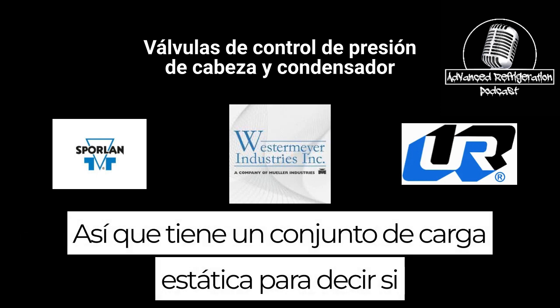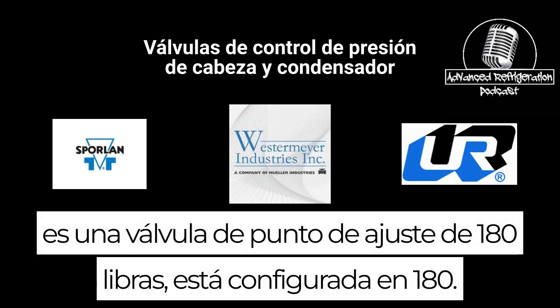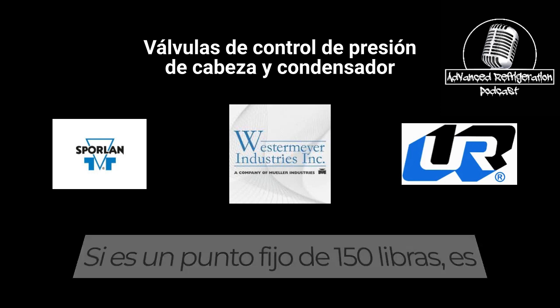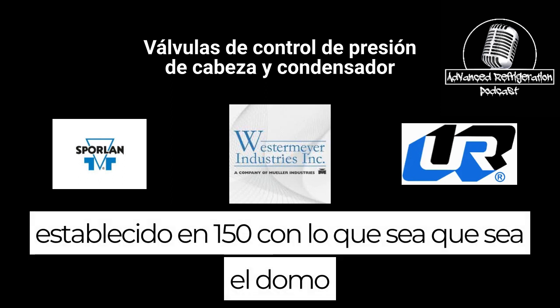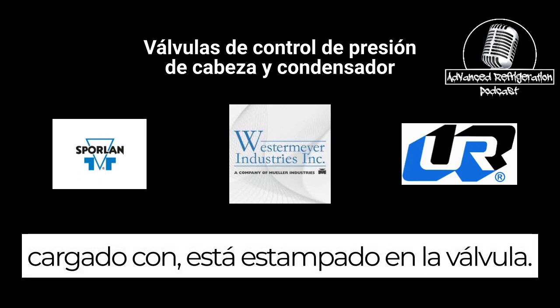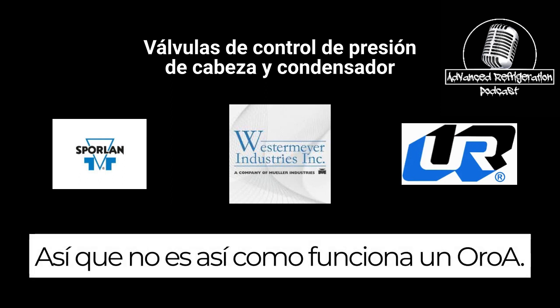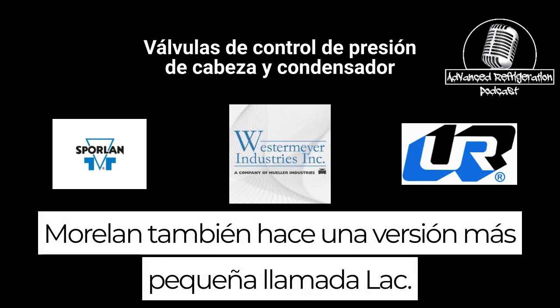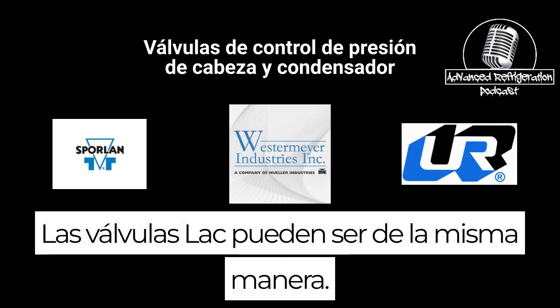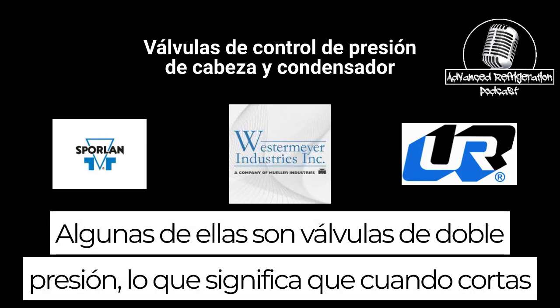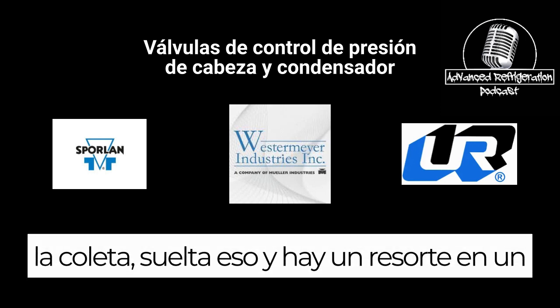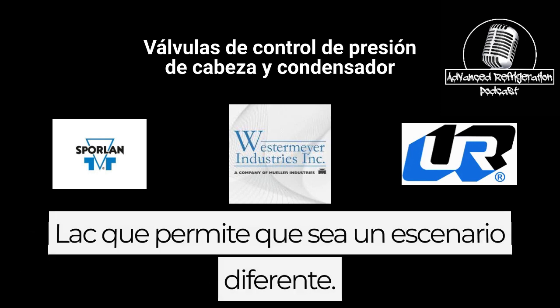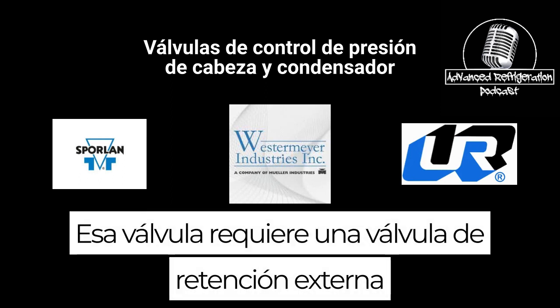So it's got a static charge. If it's a 180-pound set point valve, it's set to 180. If it's a 150-pound set point, it's set to 150, with whatever the dome is charged with, and it's stamped on the valve. So that isn't how an ROA works. Sporlan also makes a smaller version called an LAC. LAC valves can be the same way. Some of them are dual pressure valves, meaning when you clip the pigtail, it releases that, and there's a spring in an LAC that allows it to be a different setting. That valve requires an external check valve to be installed in the discharge line in order to prevent that flood back.